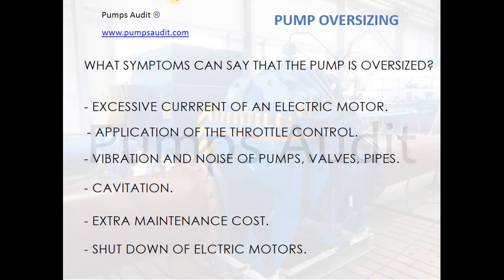How can a pump user understand that the pump is oversized? Here is the list of evidence which can indicate that the pump is oversized: excessive current of an electric motor, application of throttle control, vibration and noise of pumps, valves and pipes, cavitation in the pump, extra maintenance cost, and shutdown of electric motors.